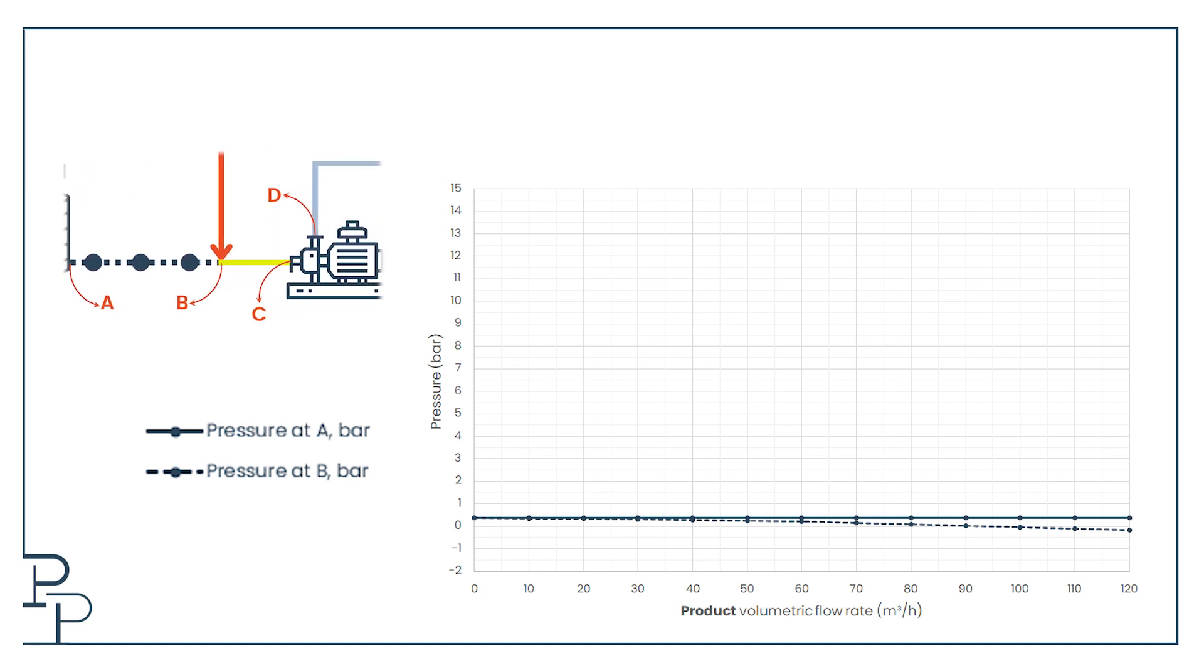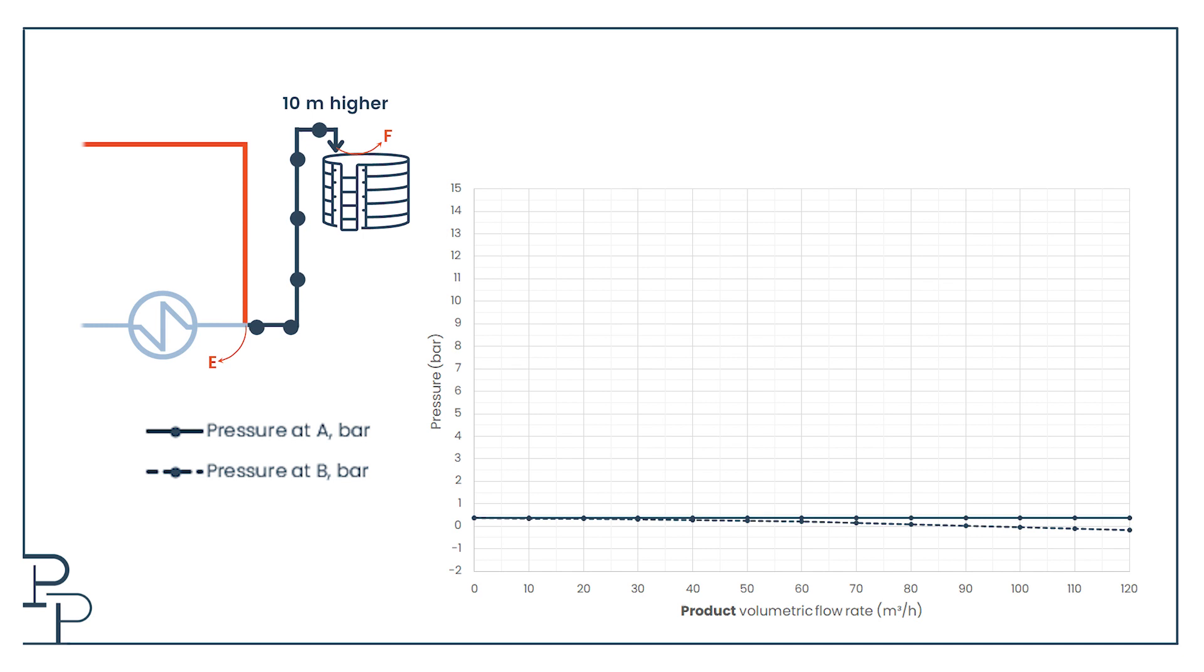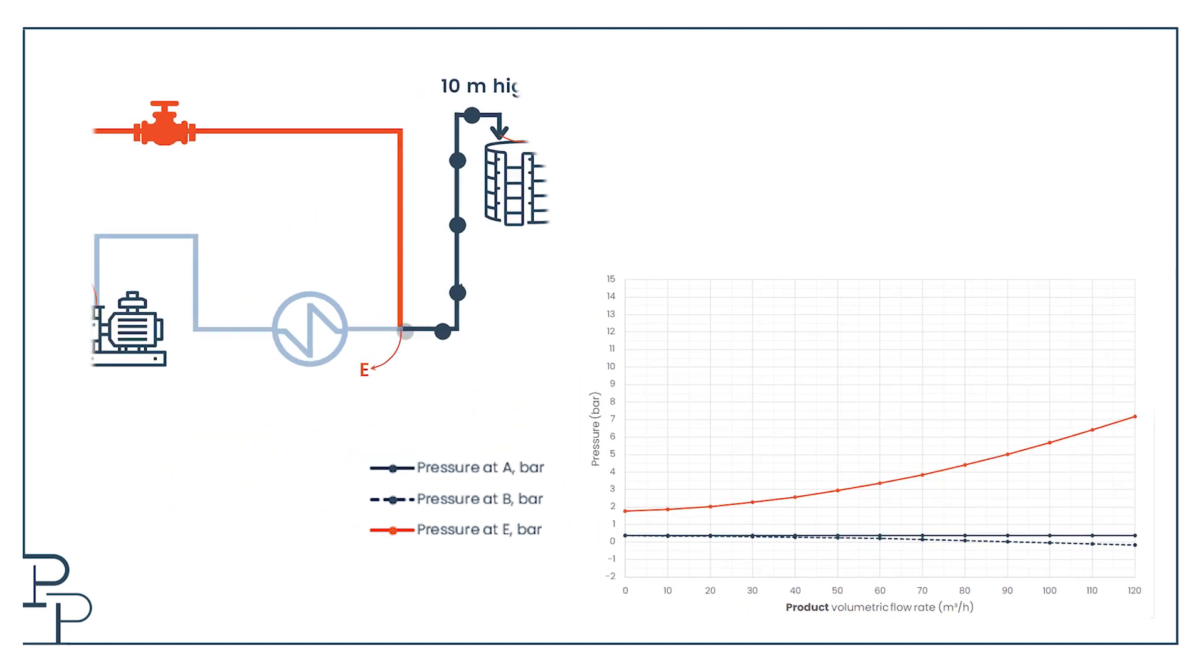Next it would be nice to calculate the pressure at C, but we simply can't do it because we're using the product flow as the basis of our calculation. We don't know what the recycle flow is and hence we don't know the flow rate through portion BC nor do we know the flow rate through DE at the discharge of the pump. It's only the pressure at point E we can calculate because the flow rate through EF is the product flow rate again after the recycle has branched off. Because point F is at atmospheric pressure, the pressure at E is equal to the pressure drop across EF. You'll notice that it starts at 1.8 bar because unless I have 1.8 bar, there is no way I can elevate sulfuric acid to a height of 10 meters.